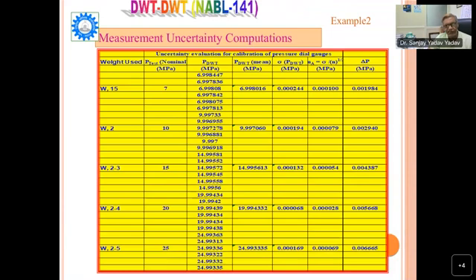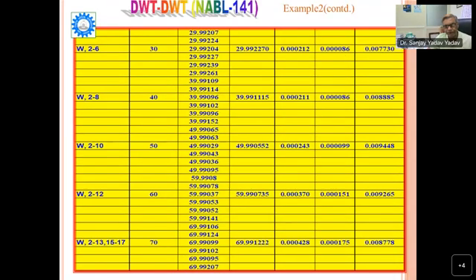Similarly, in the dial gauge, this example is given. I suppose by using the last slide, you have determined the pressure corrected value. This is the nominal value, and this is the mean value, and then sigma, and then the type A uncertainty, and then the mean value minus this. You can determine the delta P. This is as per the 141 guide.